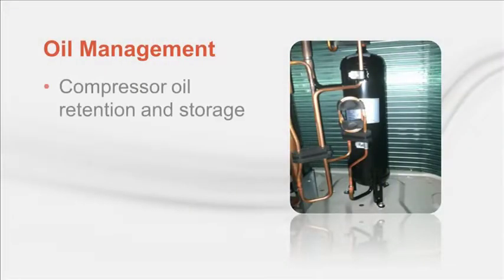Looking at all this refrigerant pipe might have you asking, what about oil return? This is a legitimate concern and an obvious question. Well, let's take a look at how VRF manufacturers handle this. First, the compressors must be designed with adequate internal storage capacity, so they have large sumps.